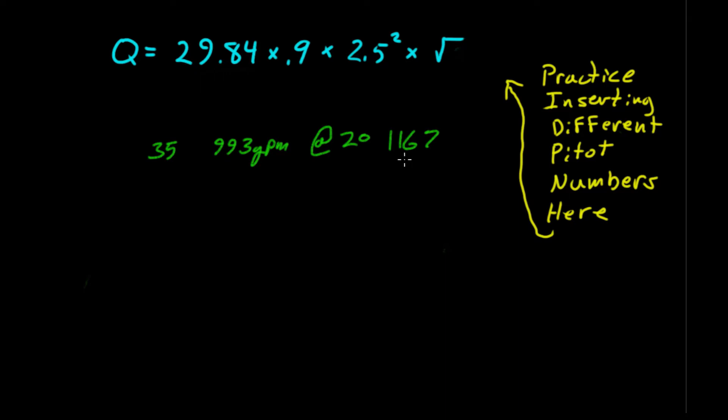And if we decided that we wanted to do one more, if you want 45 on the pitot, you should get an answer of approximately 1,126. And then your theoretical flow would be 1,323 gallons a minute.